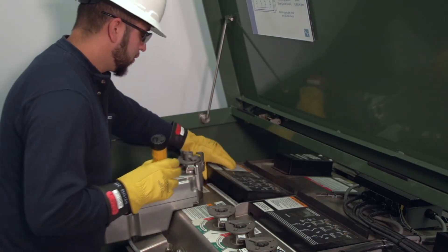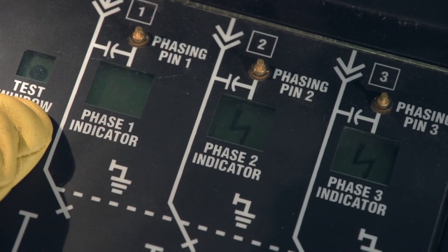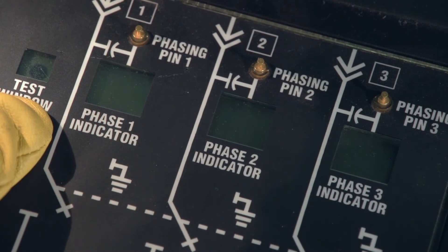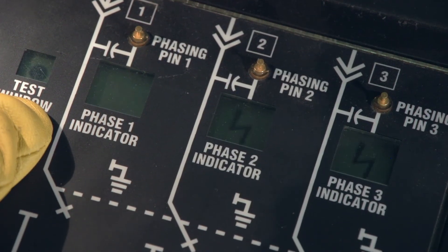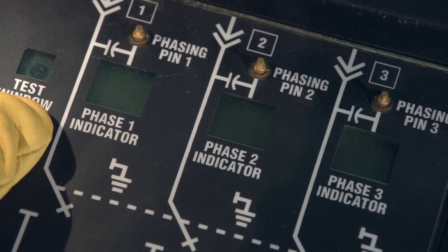The optional voltage indicator is used to check for voltage on the phases of the load interrupter switch or fault interrupter. Before using the voltage indicator, always test to make sure it is operating properly. Clean the surface of the photocell and the test button if necessary. If the photocell is dirty, the voltage indicator will be in the test mode and may give a false indication that all three phases are energized. The test mode is indicated by a dot in the test window.